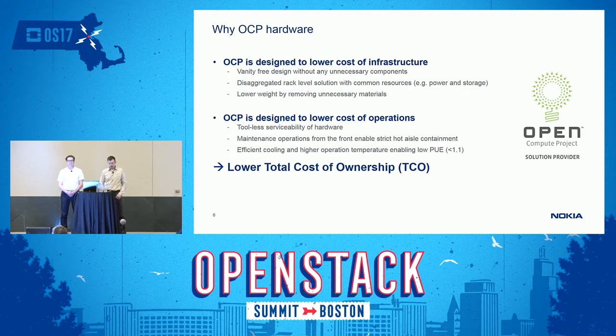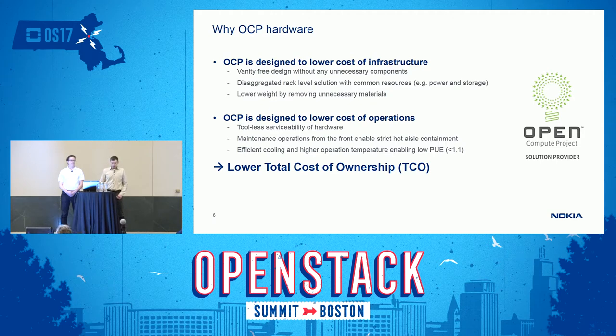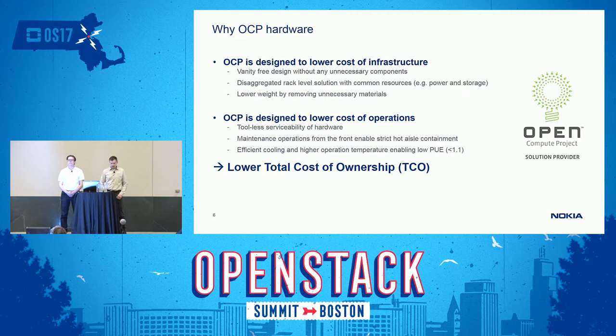And why OCP hardware? Well, OCP hardware is cost efficient — it lowers the cost of both infrastructure as well as operational expenses. It's a vanity-free design without unnecessary components and materials. This is a disaggregated rack-level solution with common resources like power. From a maintenance perspective, a major benefit is the fact that all hardware operations are easily performed from the front of the rack. There is no need to access the rear, no hot aisle isolation, and no special tools required.